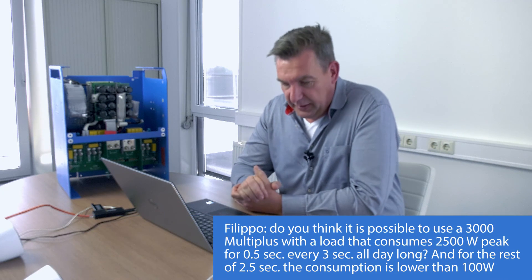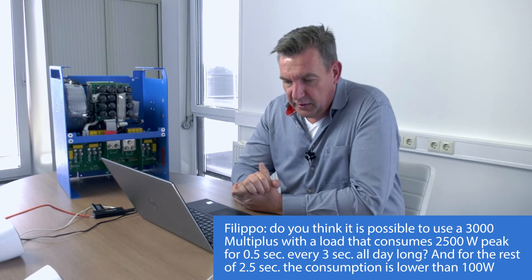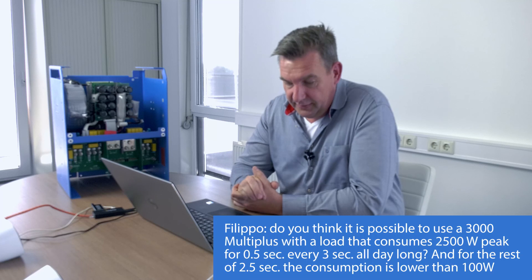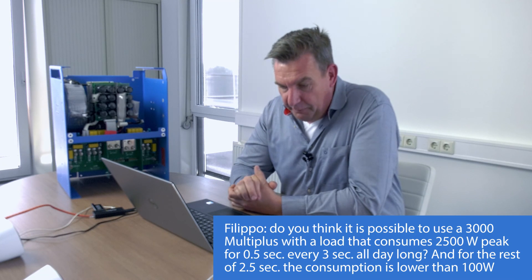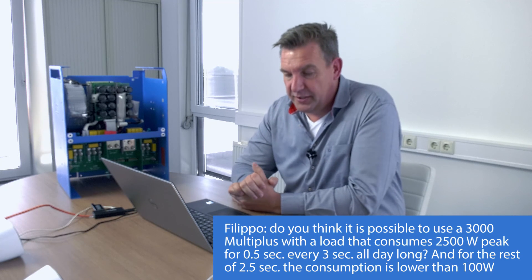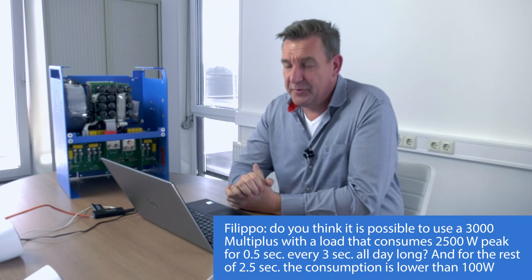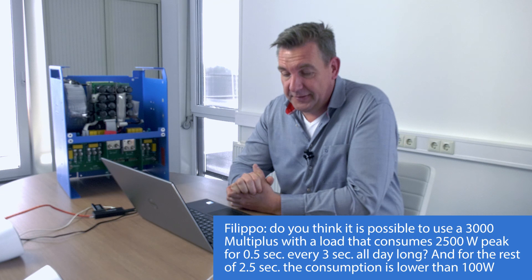Question: Is it possible to use a 3000 VA MultiPlus with a load that consumes 2500 watts peak for half a second every 3 seconds all day long, and 100 watts for the remaining two and a half seconds? A 3000 VA MultiPlus can handle a 2500-watt peak, but it depends on temperature because you're basically at the limit. Theoretically, you can do that, and 100 watts for the rest of the time is easy for the unit.